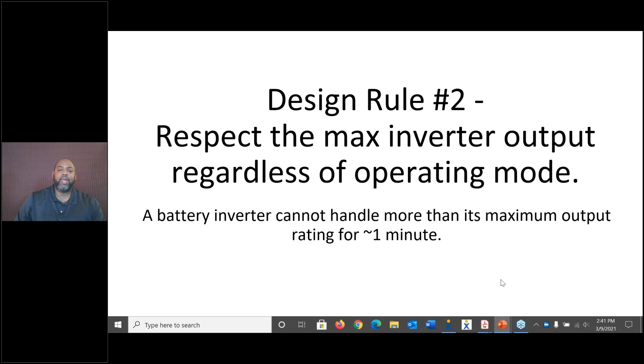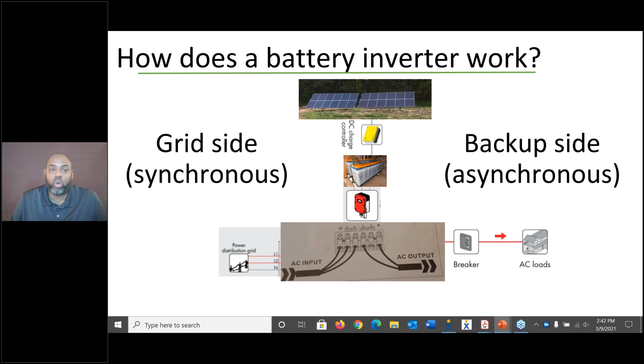So when we size up our systems, we want to make sure that we're not putting too much load on the DC side of that battery, because when you take a solar inverter, one of the principles is that a solar inverter, and I'll go to this, is synchronous. So it's synchronized with the grid side. So if we were to lose power, this whole side goes out, and then you will be over here on the battery side of the system. Well, if there is too much load being pulled or being seen by this battery, the inverter is designed to cut off. So you have to respect that. If you put too much load onto the system, you're actually biting your nose to spite your face, meaning that you're trying to have grid stability, but you're actually becoming more unstable by putting too much load onto the battery.